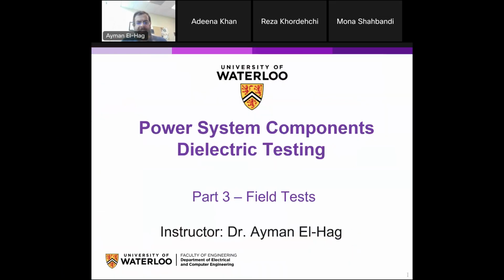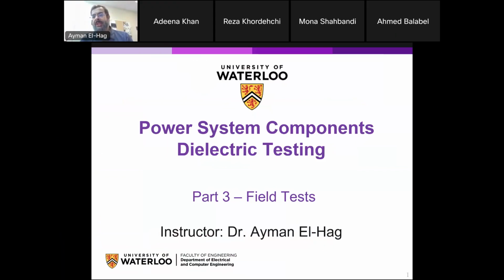So basically, today we will cover the third and the last set of notes dealing with power system component dielectric or electrical insulation testing. We talked about destructive tests, and we said that the criteria for the destructive test is either pass or fail. And then we talked about non-destructive tests, which is basically a quality test. We want to see the quality of the insulation. These two lectures were about assets in the lab when you are manufacturing it. So it's still in the manufacturer premises. Did not go to the customer yet. It's not in service yet.